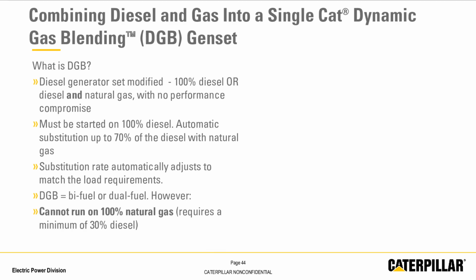So what is DGB? It's a diesel generator set which has been modified to run on either 100% diesel or a mixture of both diesel and gas without any compromise on power or transient response. It starts on 100% diesel, and then if gas supply is detected, it will automatically substitute up to 70% of that diesel with natural gas. The natural gas is fumigated into the air intake, and that's how it's entrained into the engine. It automatically adjusts the substitution rate to match the load demand.